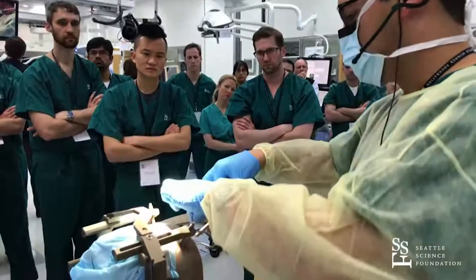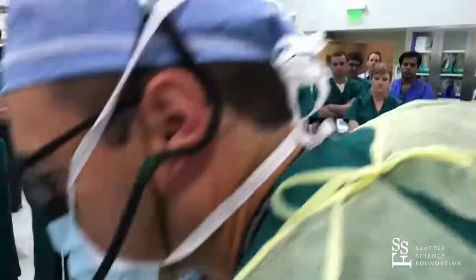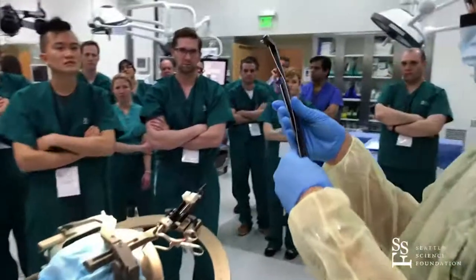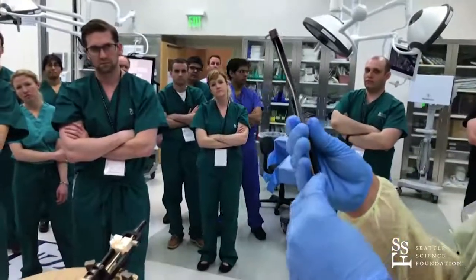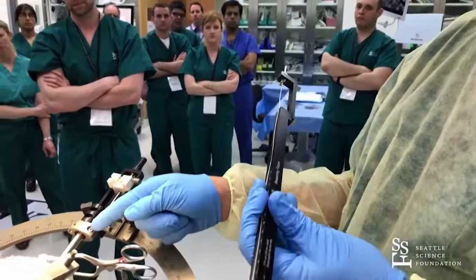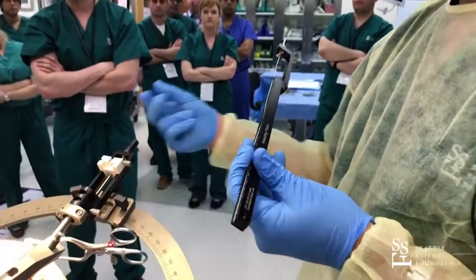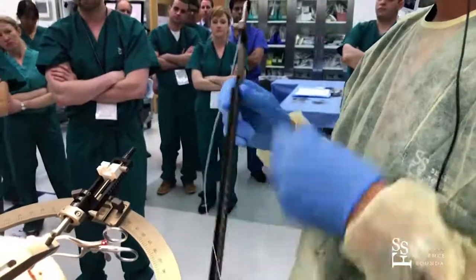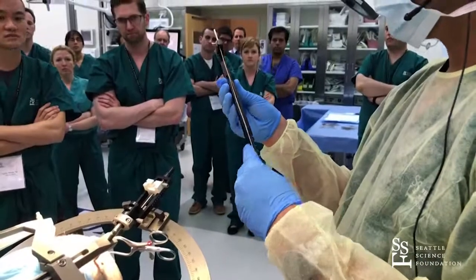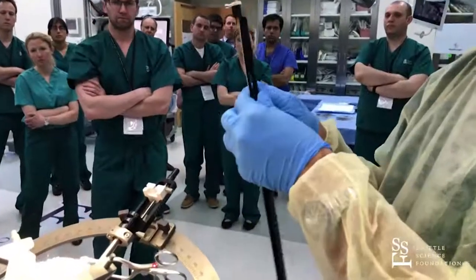So now that we have the cannula in, we've got our DBS electrode over here. Again, this is part of how the system works. This is part of the FHC Leksell combo, which is called a measuring fixture. The idea is that from the stage, when everything's centered to the center of the frame, it's 190 millimeters. We've already brought this advance 20 millimeters down. And then this star drive right here adds additional height. Basically, without having to do any calculations on your OR table, in a nutshell, what this measuring device means is that I can measure it like this.